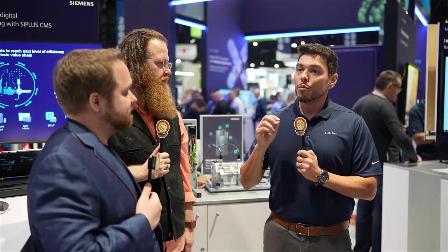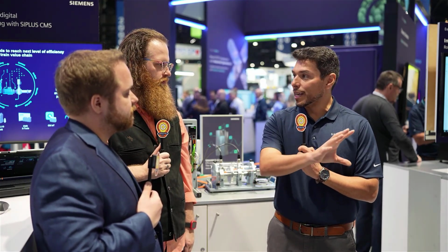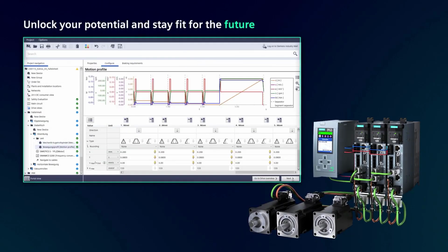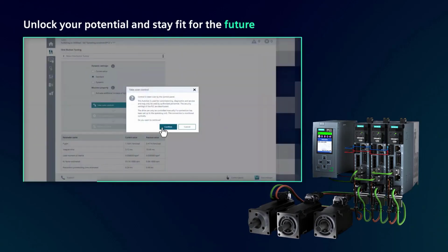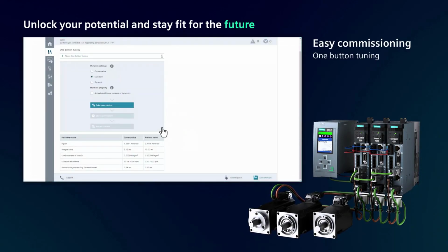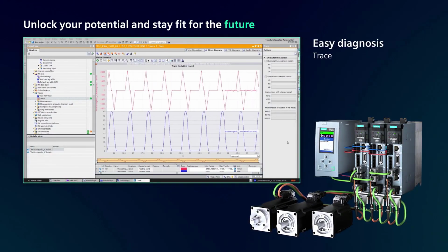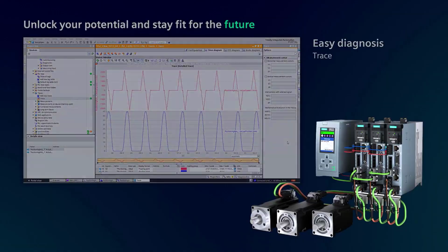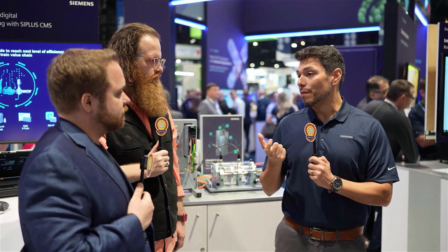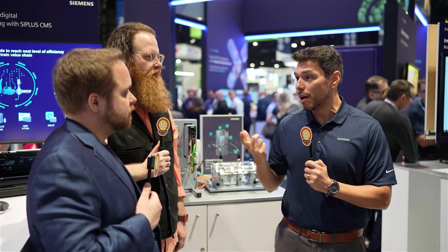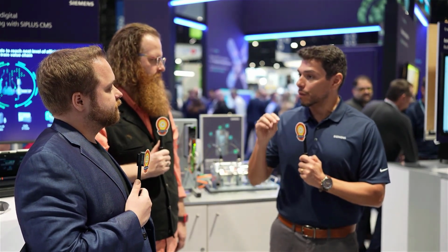What's new is really simulation, and simulation here is really handshaking data from the PLC and handshaking data from the actual physical model that you want to simulate. In the past, we had dumb drives, per se, where they didn't fully represent all the control loops that are inside of a real drive, the real firmware inside of a real drive. Now we have a block of code, a data block called DriveSim. And it's a true representation of the real firmware of the drive.